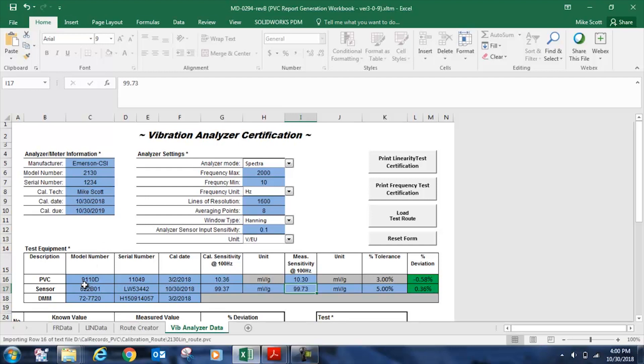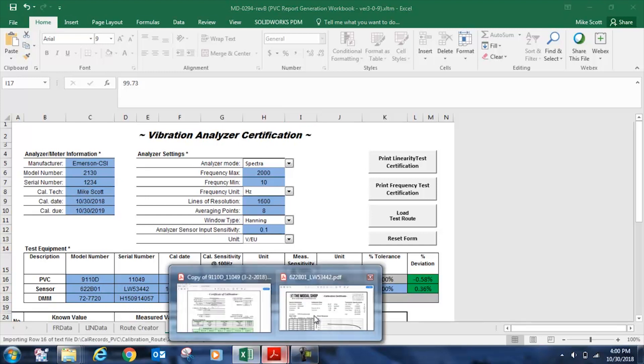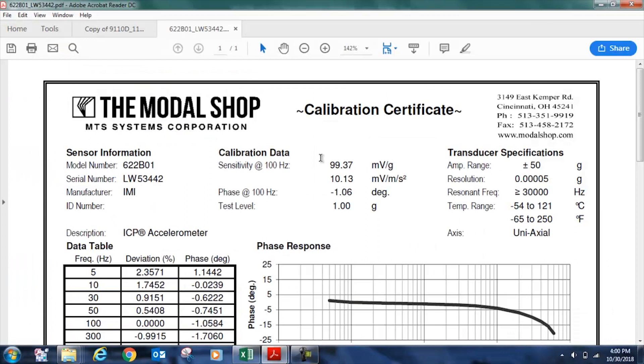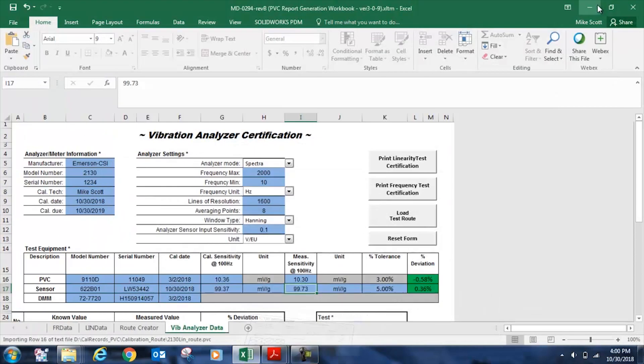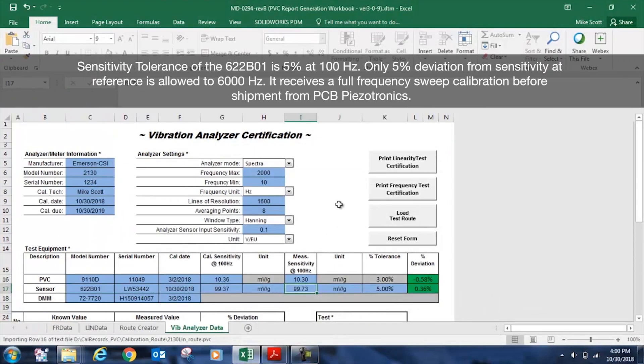We should document our accelerometer that is being used with our 2130, which is the IMI sensors 622B01. Serial number is shown there. That was calibrated on the day we shot the video, which was October 30th, 2018. And when it was calibrated, the sensitivity was 99.37 millivolts per G, as you can see here on the calibration certificate. And by the way, the 622B01 is an excellent sensor for route-based predictive maintenance because it receives a full frequency response calibration and has a very tight sensitivity tolerance.